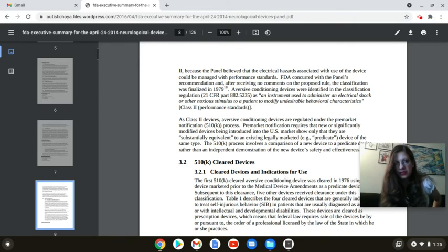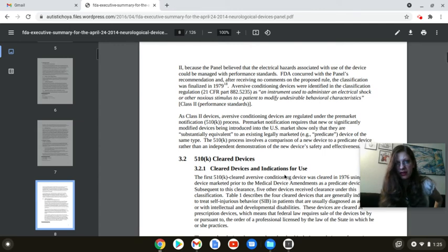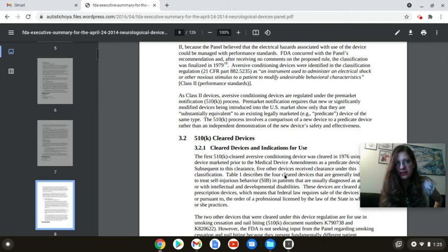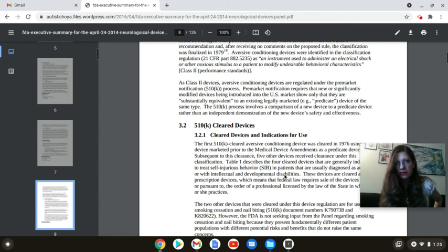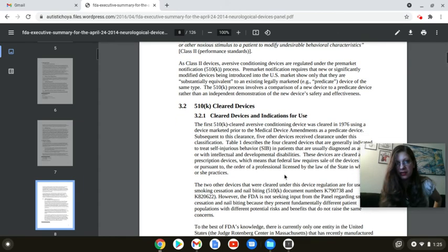As Class 2 devices, aversive conditioning devices are regulated under the pre-market notifications 510(k) process. Pre-market notification requires that new or significantly modified devices being introduced into the U.S. market show only that they are substantially equivalent to an existing legally marketed device of the same type. The 510(k) process involves a comparison of a new device to a predicate device rather than an independent demonstration of the new device's safety and effectiveness.